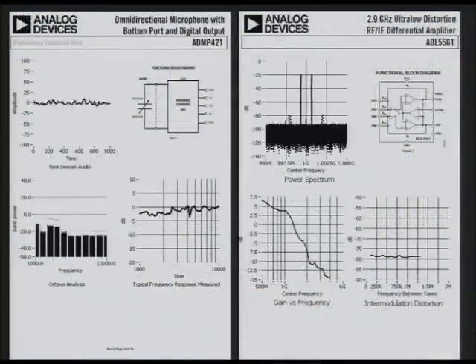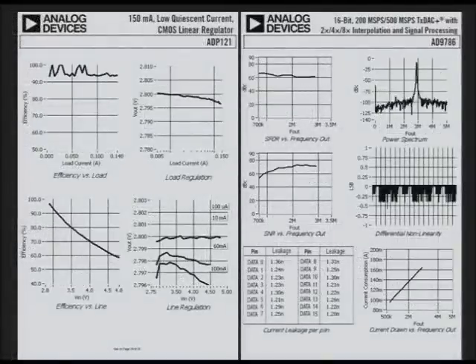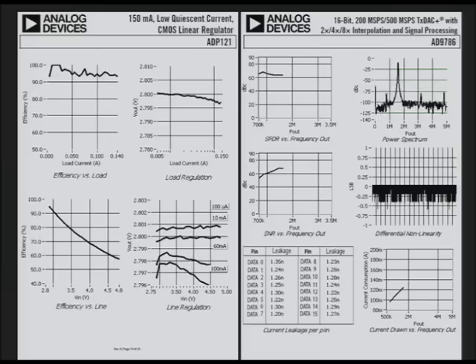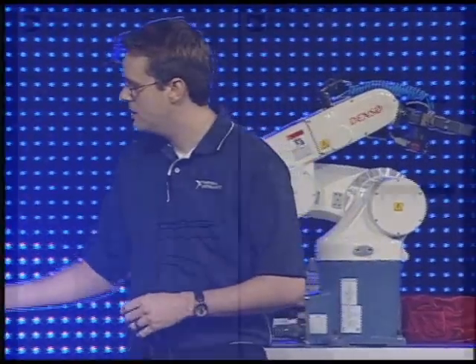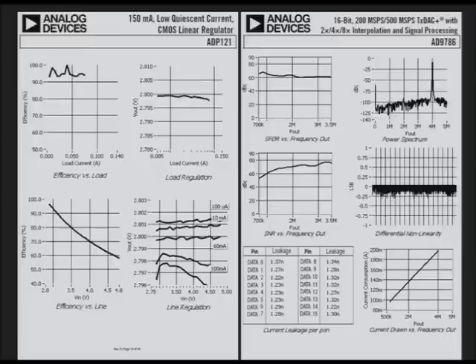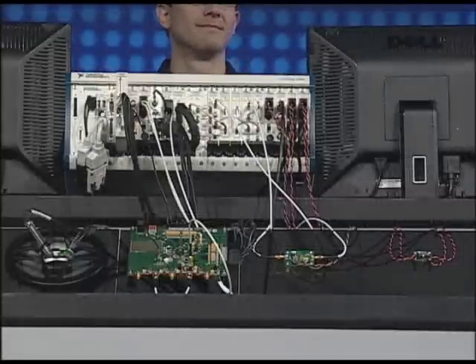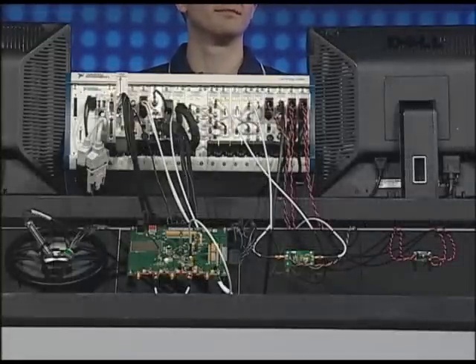So if I understand correctly, you've created a LabVIEW program with a user interface that looks like a traditional technical data sheet, but lets you look more closely at the specifications you care about. Exactly, John. I'm able to test all these devices in parallel and get the parametric data I'm interested in — for example, the IV curves of the power management IC, the spectra of the DAC and the RF IC, and a suite of audio measurements on the MEMS microphone. The modularity of the PXI platform means I can choose and synchronize all the instrumentation necessary to test all these devices in parallel.